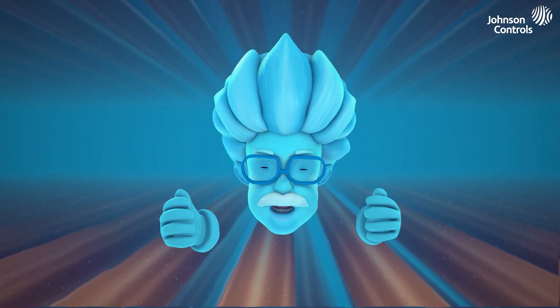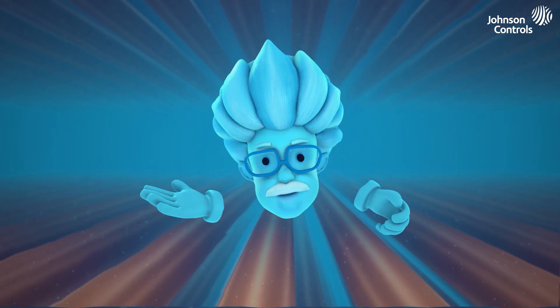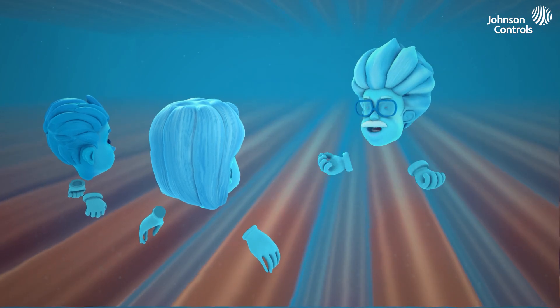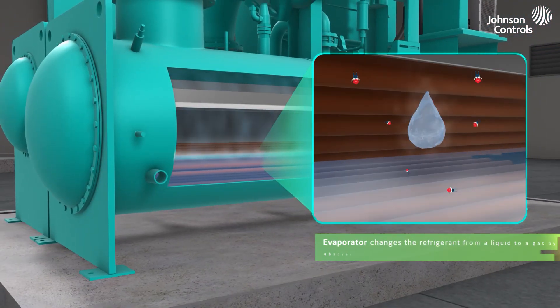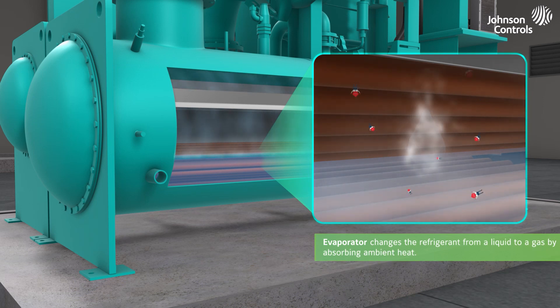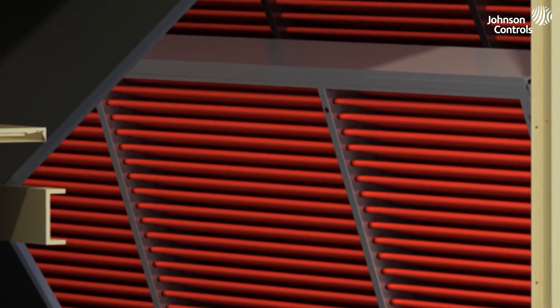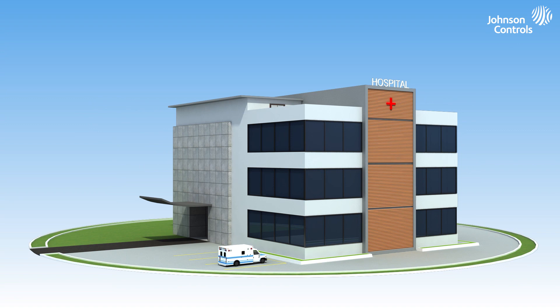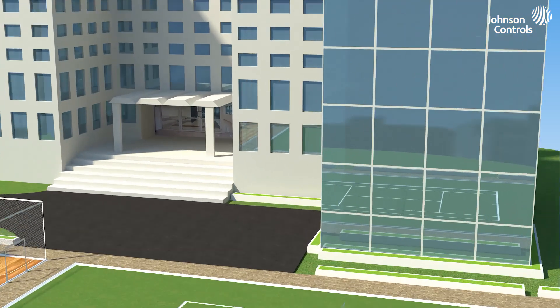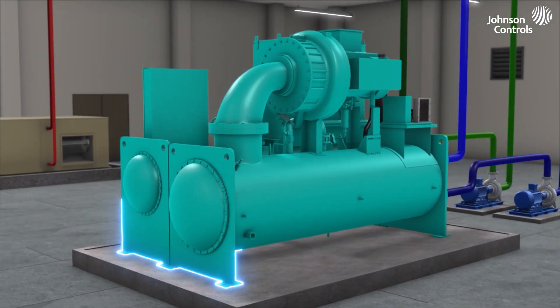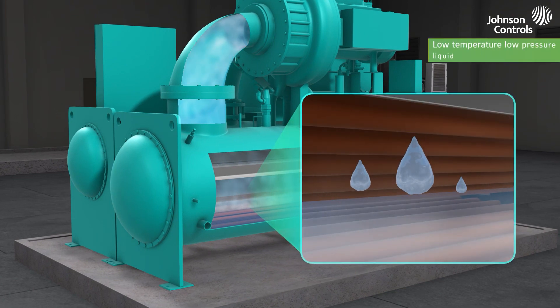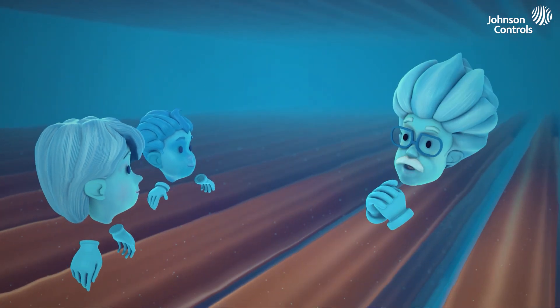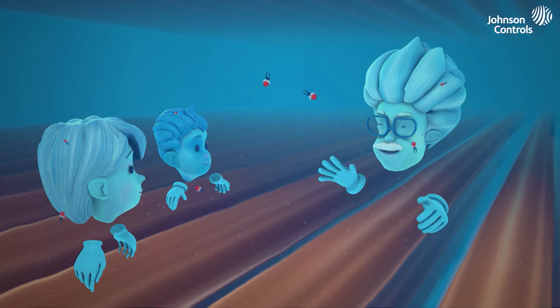The first leg of our adventure starts in the evaporator. The evaporator is responsible for changing us from a liquid to a gas by absorbing ambient heat. Evaporators can be found either in the airstream itself, such as a DX coil in an air handling unit, or for larger buildings such as hospitals and universities, they can be found in something called a chiller. That's where we are now. When we entered the evaporator, we came in as a low-temperature, low-pressure liquid. We are cooler than the chilled water flowing around us, which allows us to absorb all these BTUs, or heat, from it.